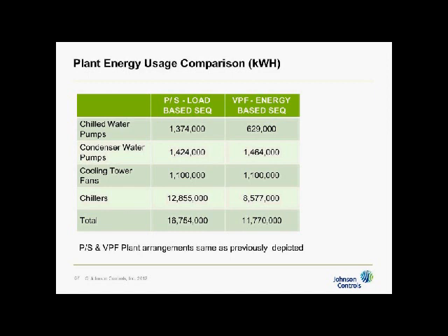Cooling tower fans were approximately the same, but now you can see the effect of energy-based sequencing on the average chiller load. Instead of 12.9 million kilowatt hours per year with the variable speed drive chiller, we now can achieve 8.6 million kilowatt hours per year, and now the total energy for that plant is 11.8 million kilowatt hours.